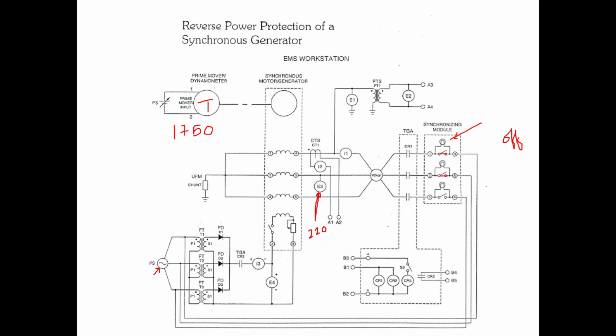When the lamps are dark, we will close these switches, and now CR1 is normally energized. So the CR1 contact is already closed. That means we have now connected the generator, we have synchronized the generator to the grid. Now the generator is supplying the rated current to the grid. This is our grid now.